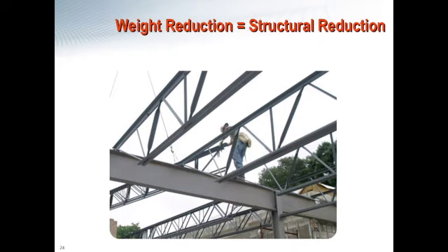So one thing that we see a lot in New York City, I go up onto roofs and I see a lot of these really giant rooftop units, whether they be modular or custom air handlers or something like that. You might have a 200-ton rooftop unit serving a building, and all of the weight for that cooling and heating provided is going to be in a centralized location. One thing that I touched on earlier is that with VRF, you're actually able to split out that weight and provide multiple systems to serve the building.